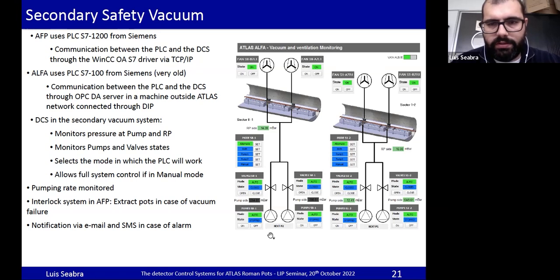So I'm showing here, for ALFA, the vacuum and ventilation panel, where we can see some pressure values in the Roman pot and on the pump side. The way it works is that we can set it to work in alternate modes: first pump 1, then in another cycle pump 2. You can have both pumps working at the same time, or select one of the pumps to be always working, or we can have a manual mode where we can just do it as we want.